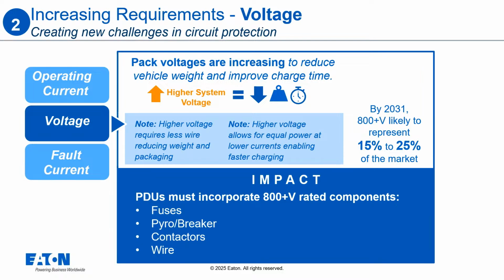Looking ahead to 2031, estimates suggest that systems operating at 800 plus volts could make up between 15% and 25% of the market. This means components like fuses, pyro switches, breakers, contactors, and even the wiring itself within power distribution units must be rated for 800 plus volts.